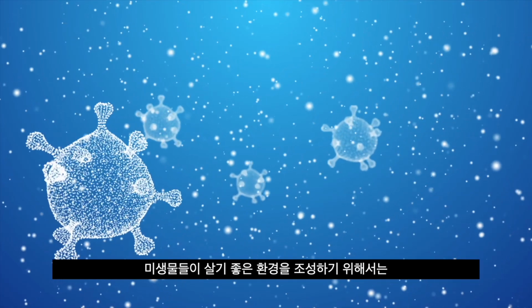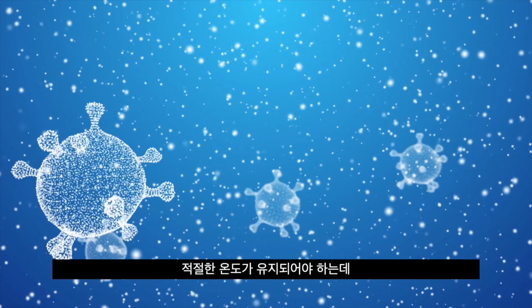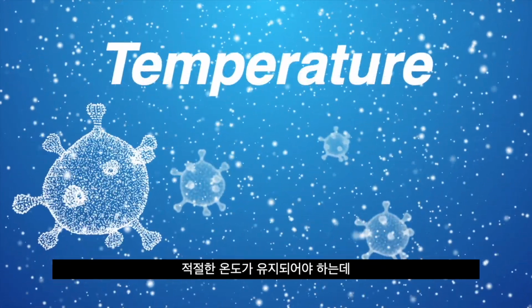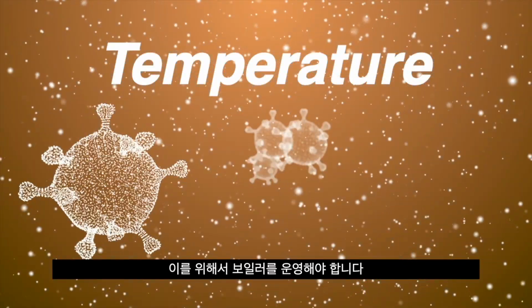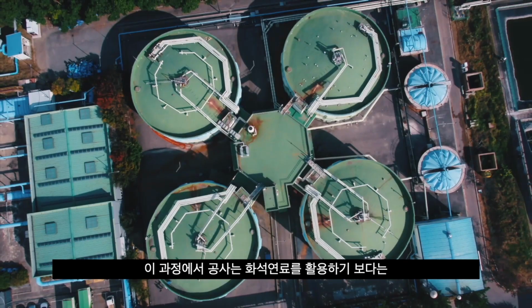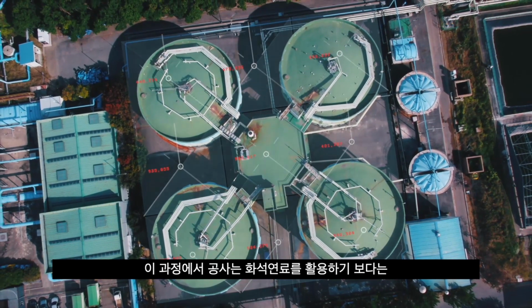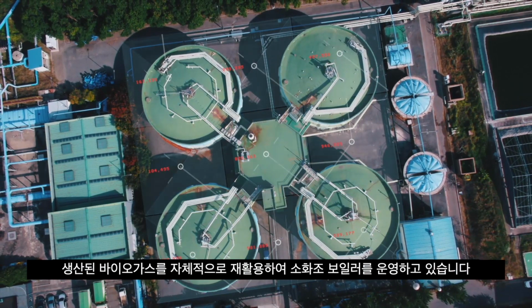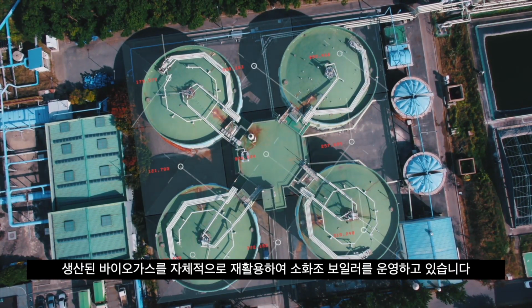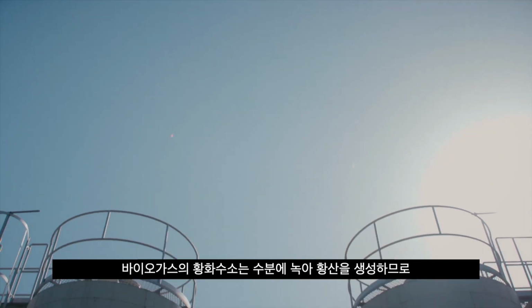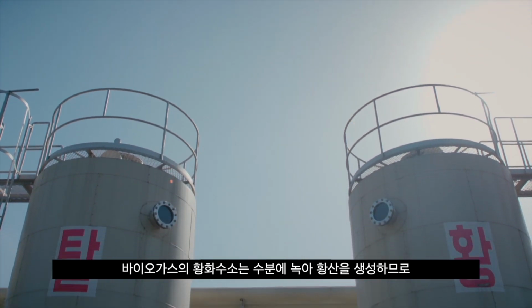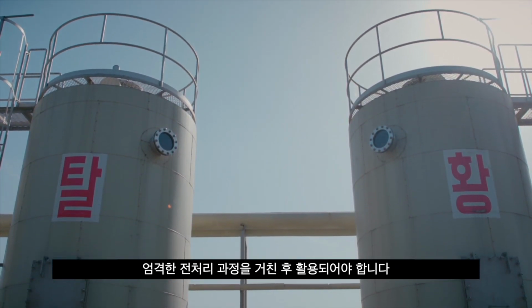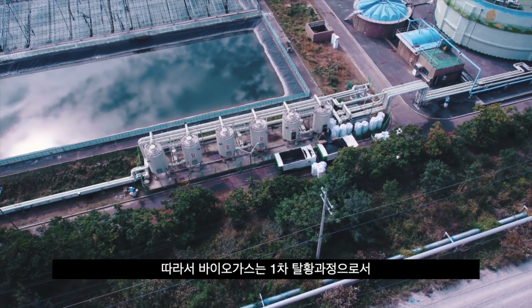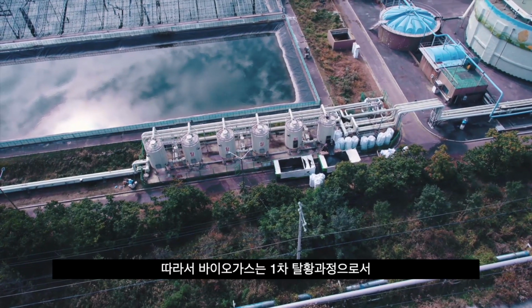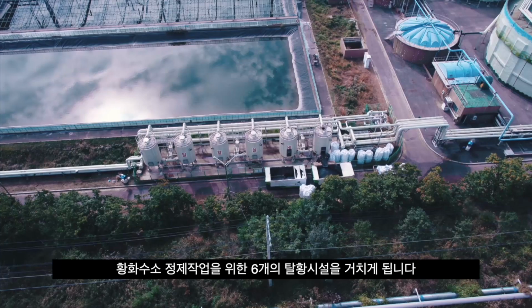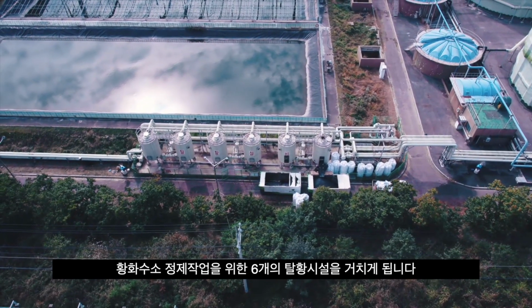In order to create an environment in which microorganisms can live, an appropriate temperature must be maintained, and for this purpose, a boiler must be operated. In this process, SLC is operating a digester boiler by recycling the biogas produced by itself, rather than using fossil fuels. Hydrogen sulfide in biogas dissolved in water produce sulfuric acid, so it must be used after a strict pretreatment process. Therefore, biogas goes through 6 desulfurization facilities for purification of hydrogen sulfide as the first desulfurization process.